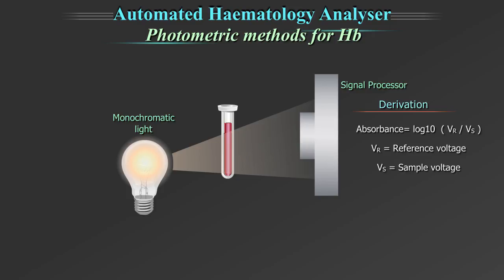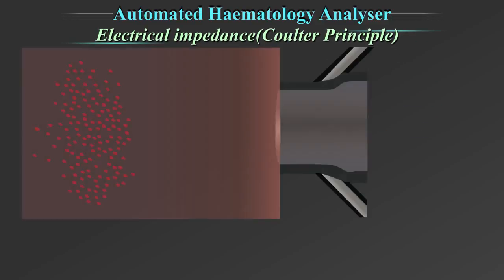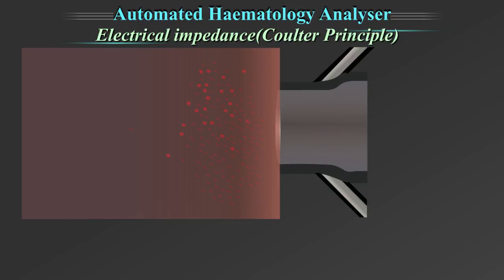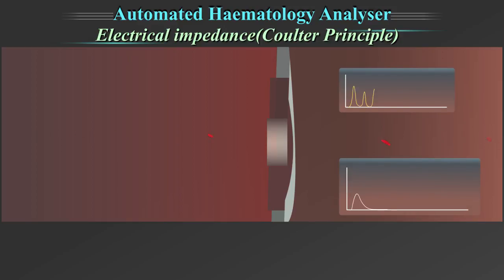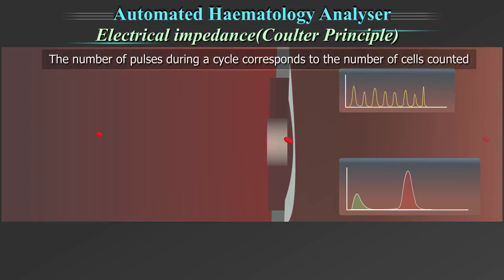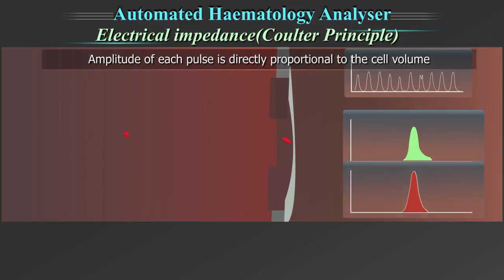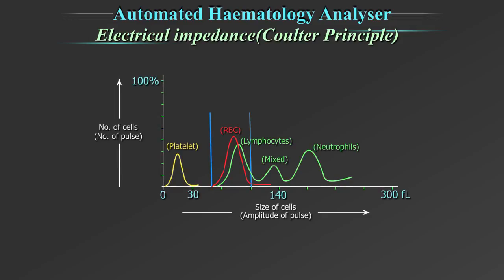The absorbance of the solution is measured by a photosensor in the hemoglobin flow cell, calculating the hemoglobin concentration. Second is electrical impedance, also known as the Coulter principle, which is used to count white blood cells, red blood cells, and platelets as they pass through an aperture. As each cell is drawn through the aperture, a change in electrical resistance occurs, generating a voltage pulse. The number of pulses during a cycle corresponds to the number of cells counted, whereas the amplitude of each pulse is directly proportional to the cell volume. The different cell components are depicted in respective histograms as per their size distribution.